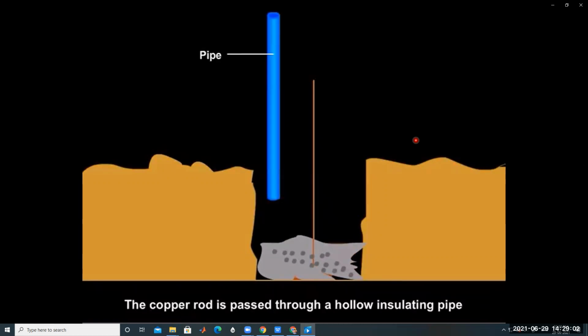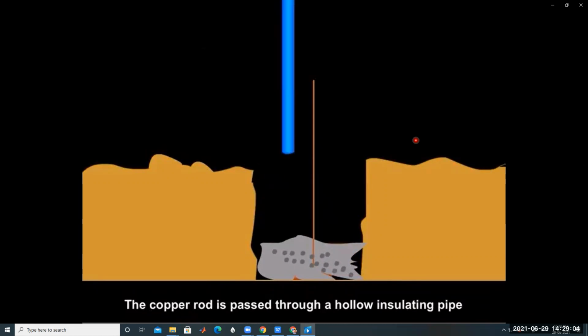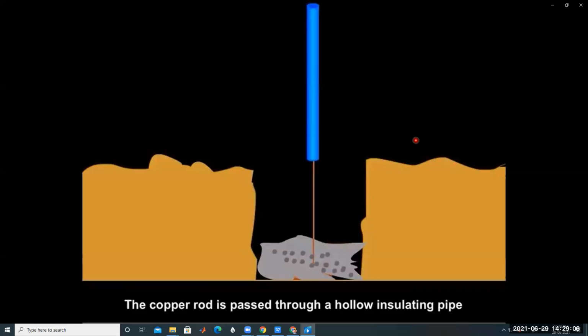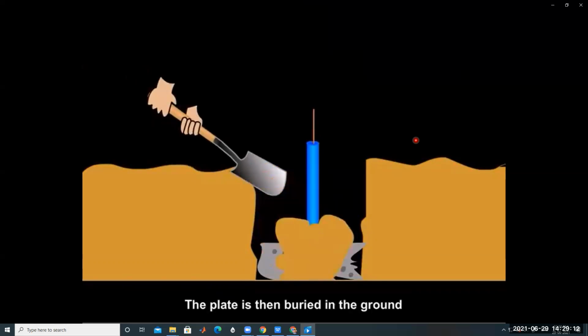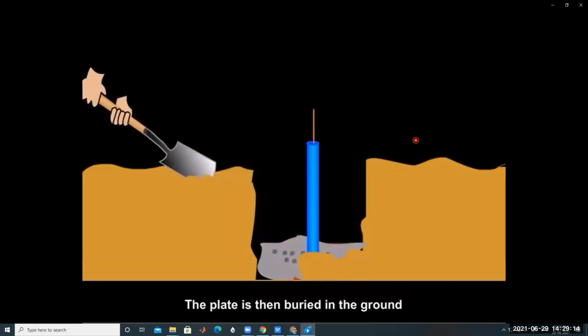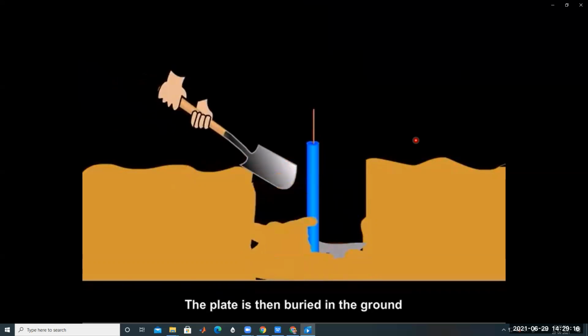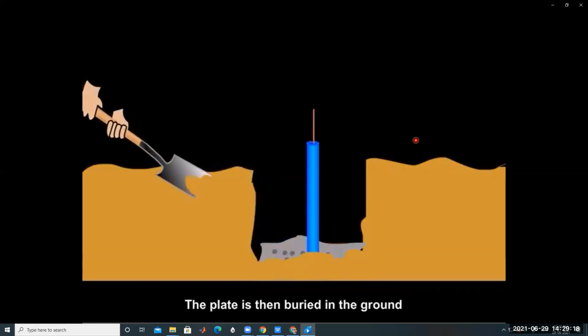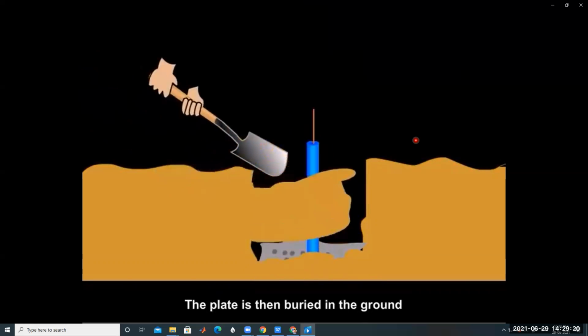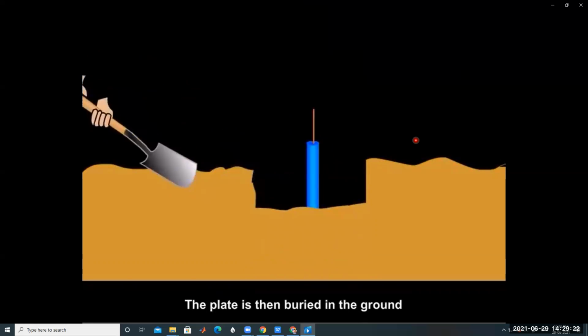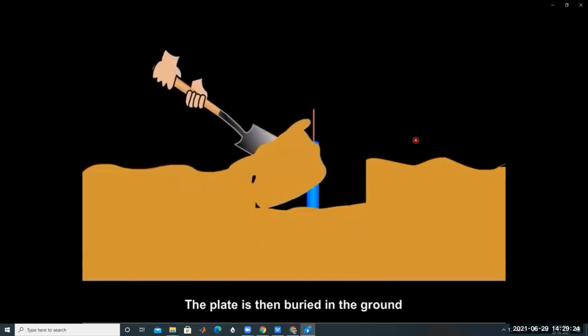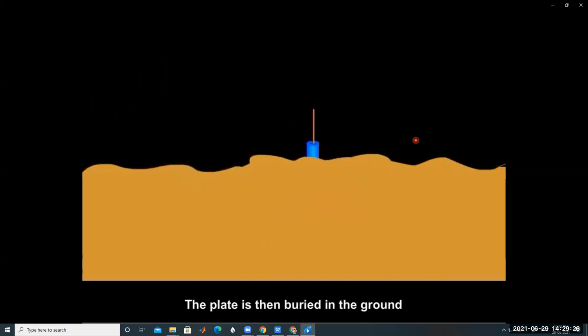And one GI pipe is placed. The GI pipe surrounds the copper rod. The copper rod is passed through a hollow insulating pipe to protect the rod. The copper plate is then buried into the ground. So the copper rod can be protected by using this plastic pipe.